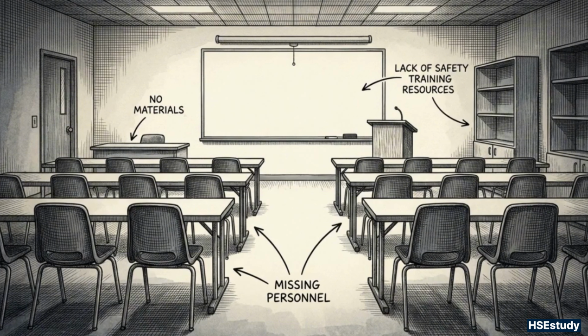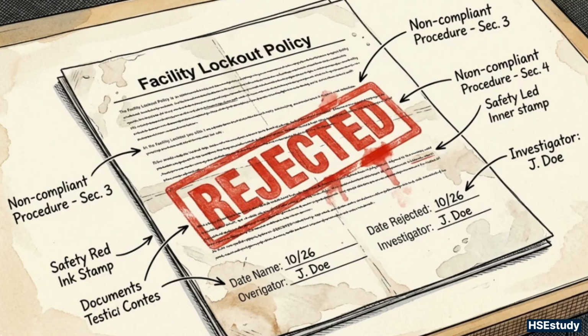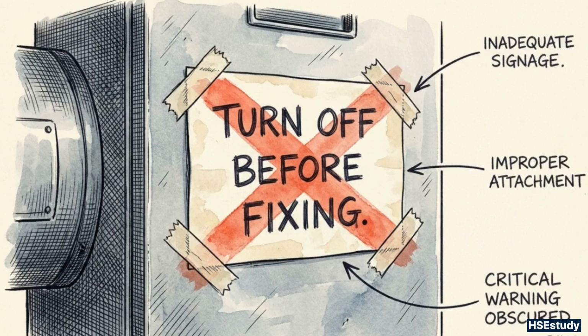OSHA found the facility lacked adequate safe work practices and failed to provide electrical maintenance training to its employees. Specifically, the company failed to maintain and execute written, machine-specific lockout-tagout procedures, directly violating 29 CFR 1910.147. A generic facility-wide LOTO policy is legally and physically insufficient.